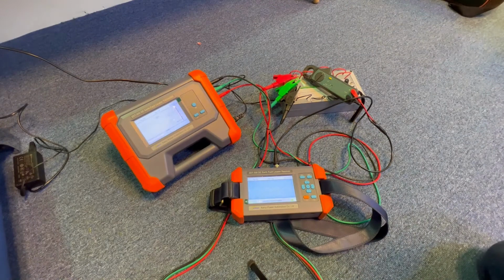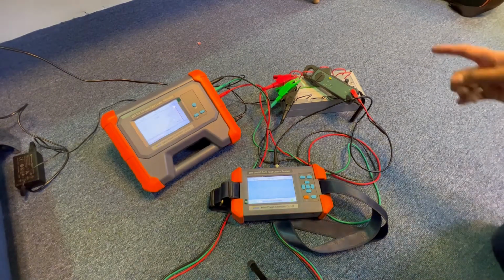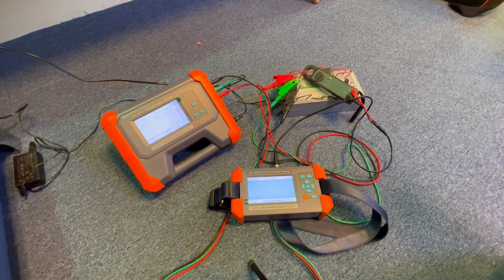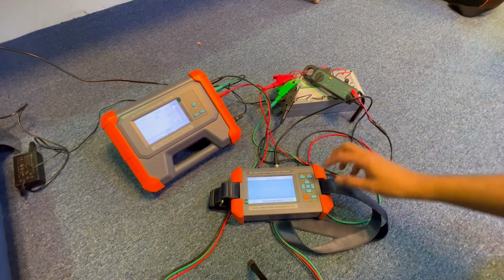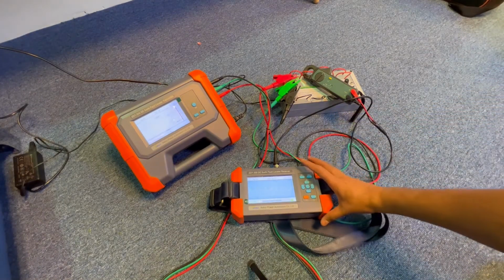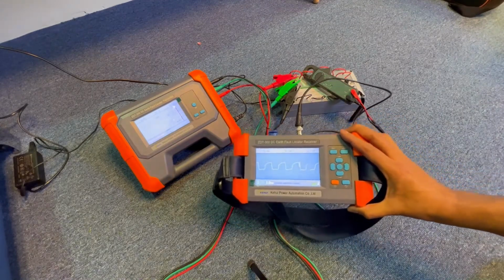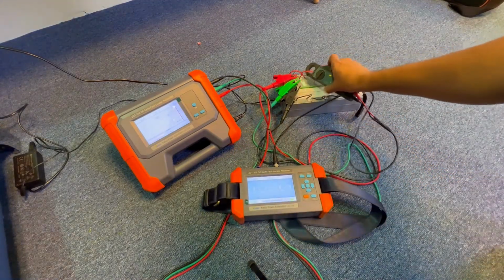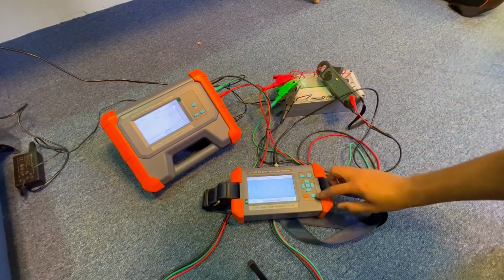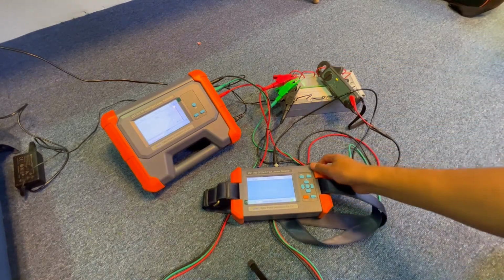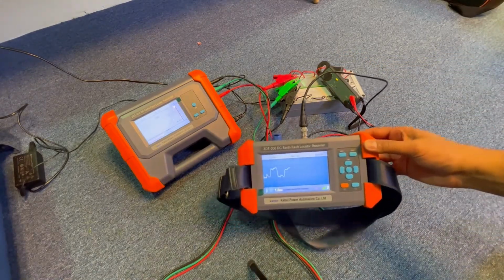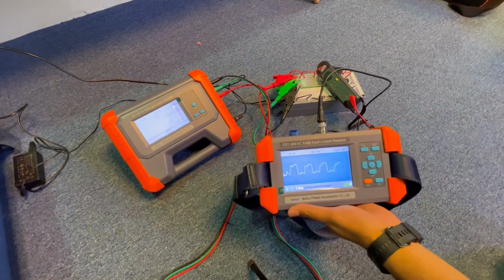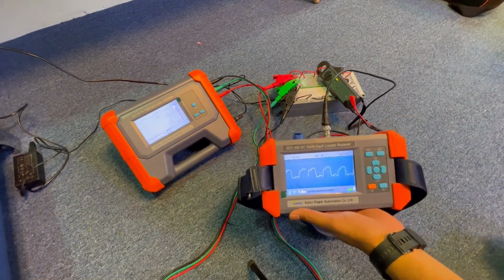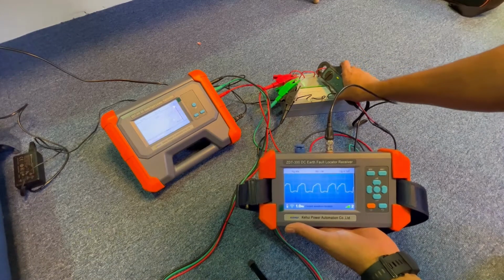So it is like a loop connection. You go panel to panel and then you go until the fault point. So this will help you to identify the feeder and also take you to the exact fault point. You can increase the signal strength here to see whether it is faulty or not. Then let's go to the next feeder. Refresh. You can still see that there is a fault continuation happening. Okay, so the fault is still in the 4th.